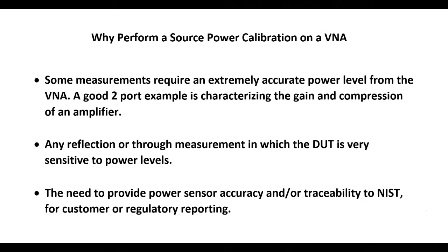For a one-port example, if you're measuring the reflection coefficient of any device that has an active component that's sensitive to power levels on the input, knowing the applied power level can be very, very critical. You might also be performing some testing where your customer or regulatory agency requires traceability to NIST or certification of some sort that's provided with power sensors. This can be very handy in a report and may be required in some instances.